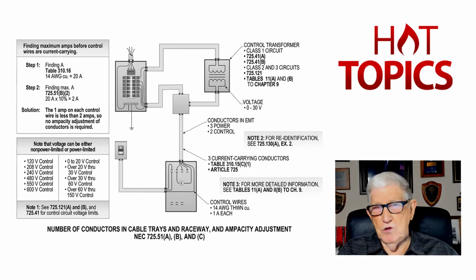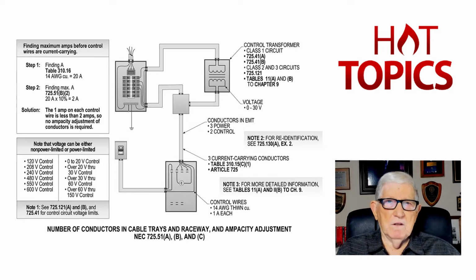But notice you have to look at 725.130(A), Exception 2. Many times folks want to know, if we have a control circuit routed with the phase conductors, and you had 5 of them, a lot of engineers, electricians, inspectors say, now you've got a derate. Well, no. You would go over and look at Table 310.16 in the NEC, and if you had number 14 20-amp conductors, you see in the left-hand side of the illustration at the very top, take 10% of it from 725.51(B) as in boy, 2, and you have 2 amps.